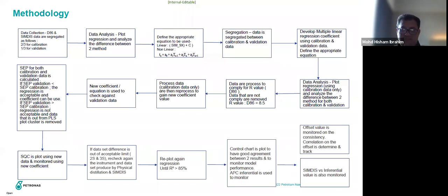After that, the process data is reprocessed to gain a new coefficient value. The new data is then checked against the validation data. The standard error of prediction, SEP, for both calibration and validation data is calculated. If the standard error of prediction for validation is less than that for calibration, the regression is acceptable and the coefficient can be used. However, if it is otherwise, where the standard error of prediction for validation is more than calibration, we cannot accept the regression, and data that is out of the partial least squares plot cluster is to be removed.